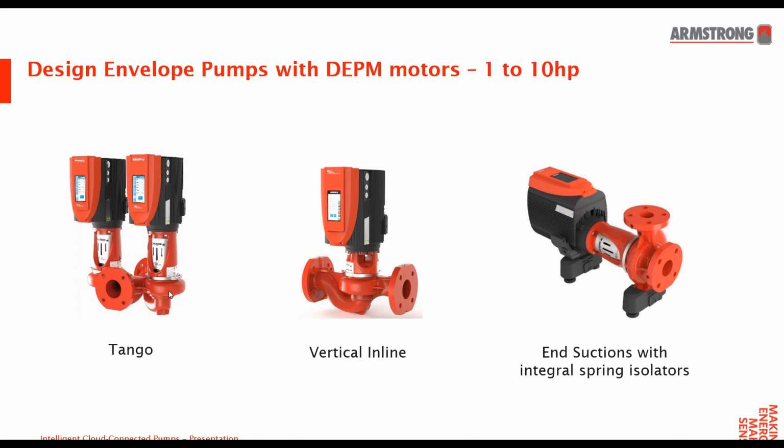That's a good question. So our recommended installation for any of our vertical pumps is that they do not include the flex connectors. They are rigidly mounted to the piping. And because of the weight of the overall piping, plus the weight of the pump and motor, and the weight of the piping all filled with water, the pump becomes part of the piping installation. It's fairly small in comparison to the overall weight of the whole piping system filled with water. And that's why you don't require the flex connectors on the vertical pumps.